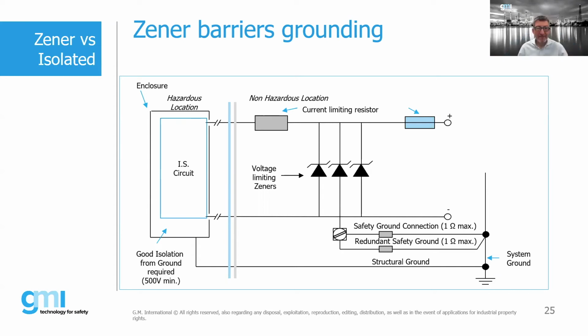All right. And by the way, regarding the size of the grounding conductor, generally speaking, if you're using two safety grounds like what you're doing here, in the IEC world, based upon -14, the minimum conductor must be 1.5 millimeter. If we're only using a single ground, then it must be at least 4 millimeter. And it may have to be larger in order to achieve that 1 ohm resistance or less.